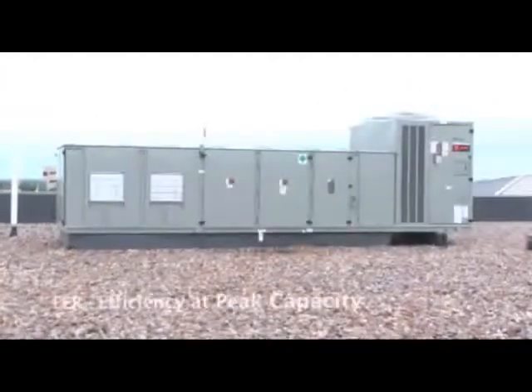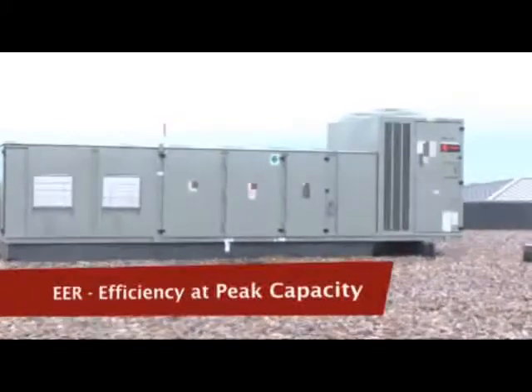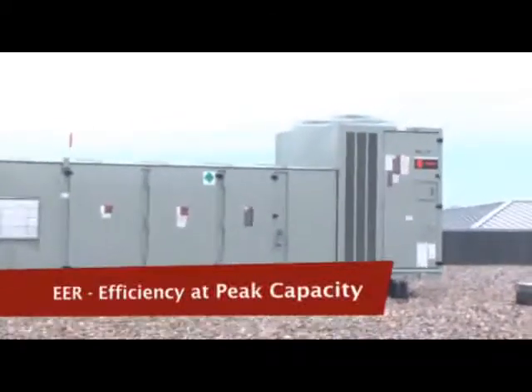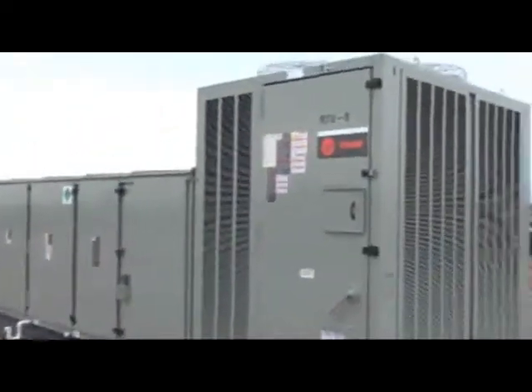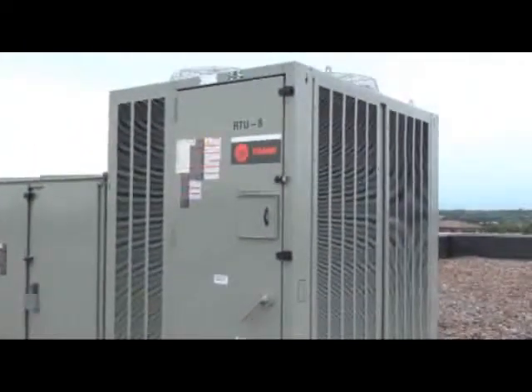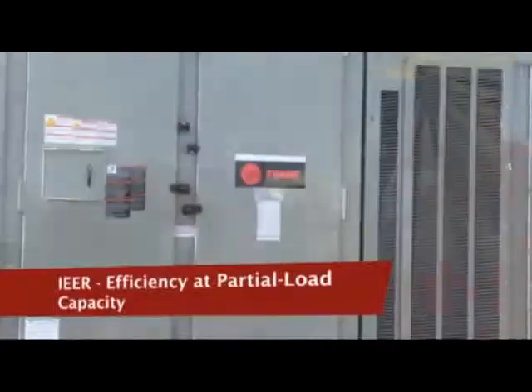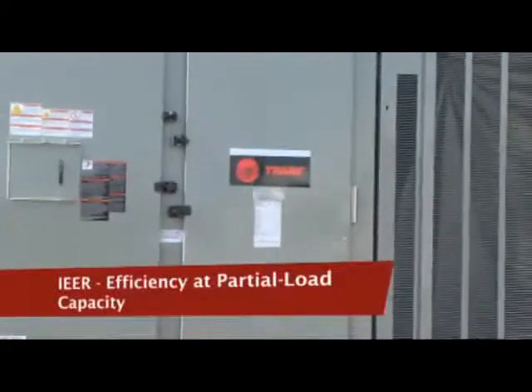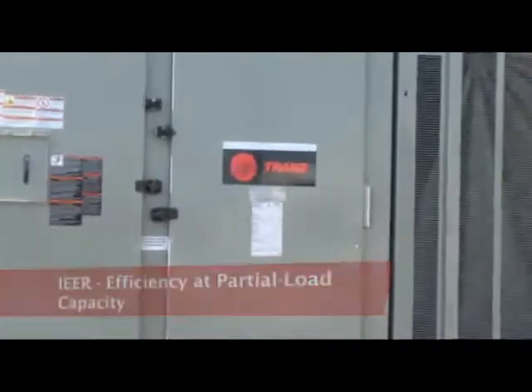The EER rating established by the Air Conditioning, Heating and Refrigeration Institute measures efficiency at peak capacity, but rooftop air conditioners only run at peak capacity about 5% of the time. So in 2010, the AHRI established a new rating system: the Integrated Energy Efficiency Ratio, or I-EER, which measures efficiency at the far more common partial load state.